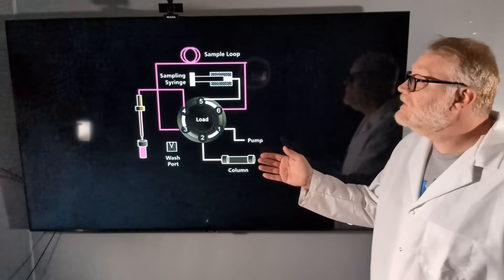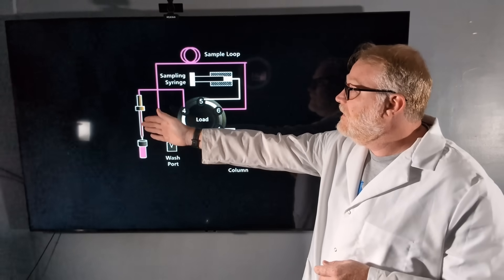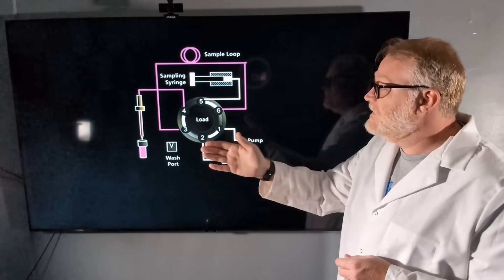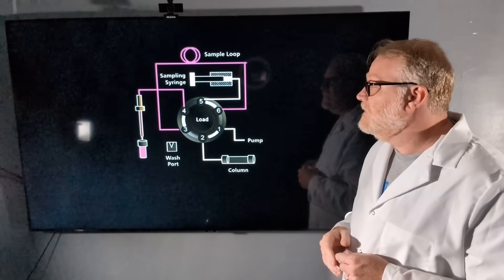Here's an example of our pull-to-fill autosampler. Here we have our sample vial, our needle, our sample loop, sampling syringe, our injection valve is in the load position, our pump, and our column.